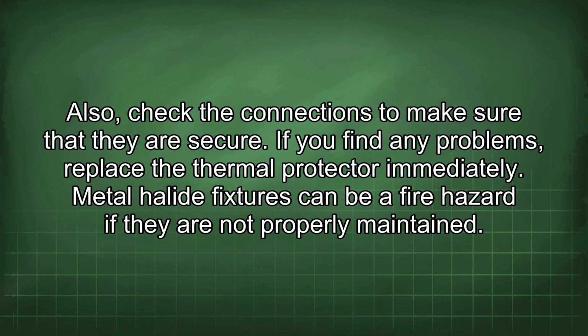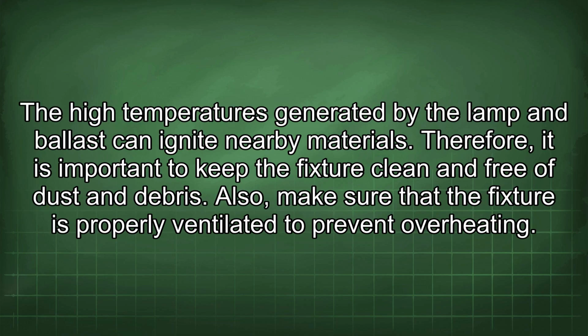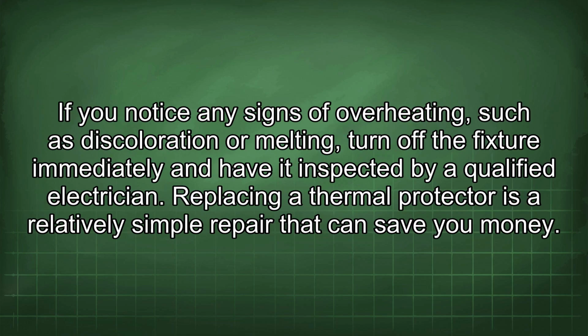Metal halide fixtures can be a fire hazard if they are not properly maintained. The high temperatures generated by the lamp and ballast can ignite nearby materials. Therefore, it is important to keep the fixture clean and free of dust and debris. Also, make sure that the fixture is properly ventilated to prevent overheating. If you notice any signs of overheating, such as discoloration or melting, turn off the fixture immediately and have it inspected by a qualified electrician.